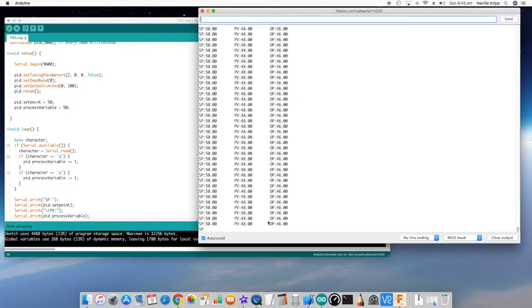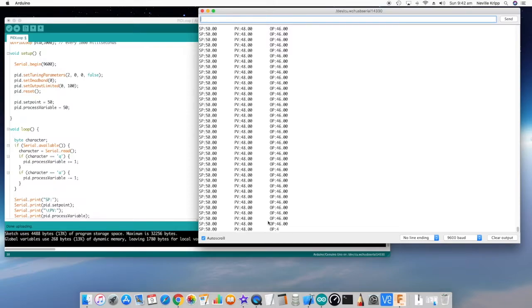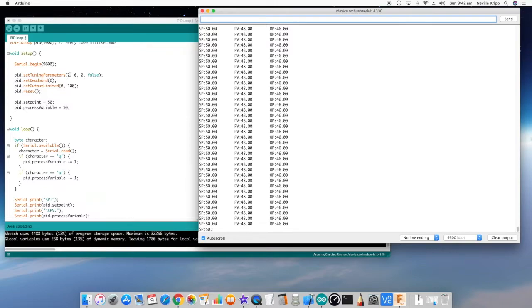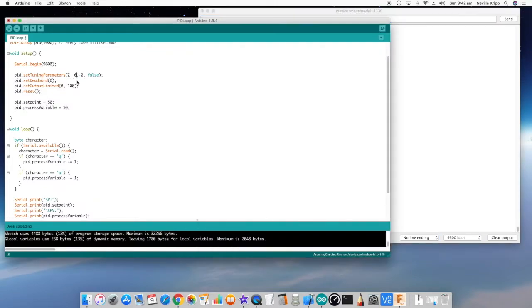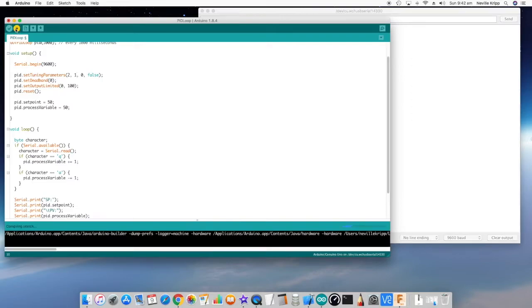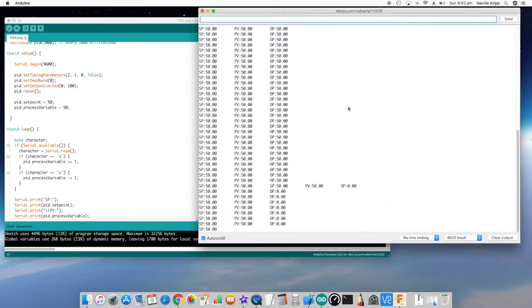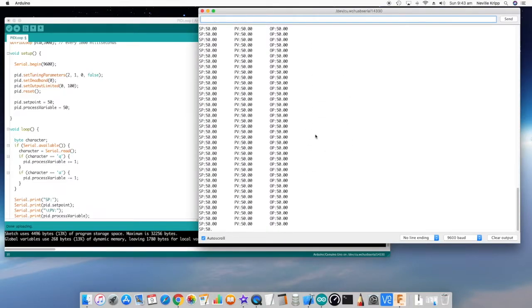So with an error of 2, I have an output difference of 4. That's an example of how the proportional gain can affect the output based on the error between set point and PV. So let's just leave that at 2 at this point in time and let's set a value of 1 in the integral term.